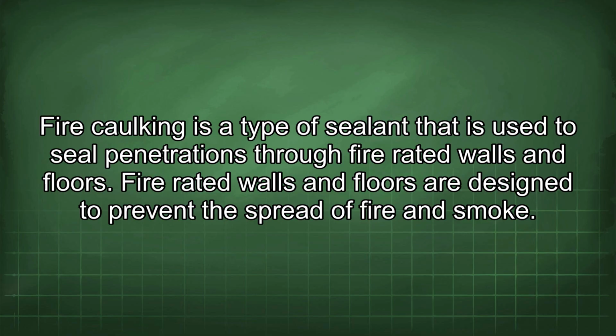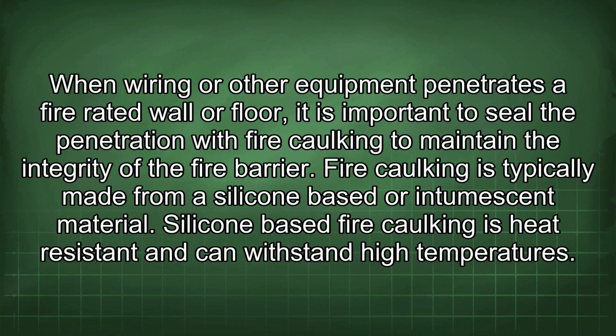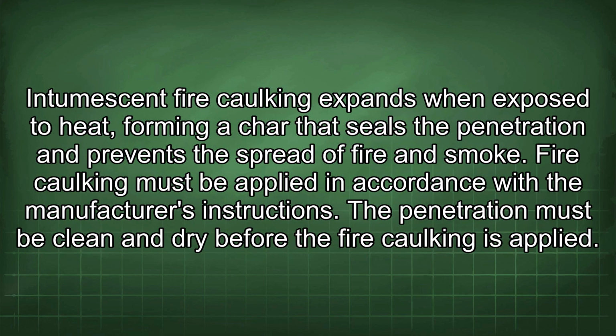Fire caulking is a type of sealant that is used to seal penetrations through fire-rated walls and floors. Fire-rated walls and floors are designed to prevent the spread of fire and smoke. When wiring or other equipment penetrates a fire-rated wall or floor, it is important to seal the penetration with fire caulking to maintain the integrity of the fire barrier. Fire caulking is typically made from a silicone-based or intumescent material. Silicone-based fire caulking is heat-resistant and can withstand high temperatures. Intumescent fire caulking expands when exposed to heat, forming a char that seals the penetration and prevents the spread of fire and smoke.